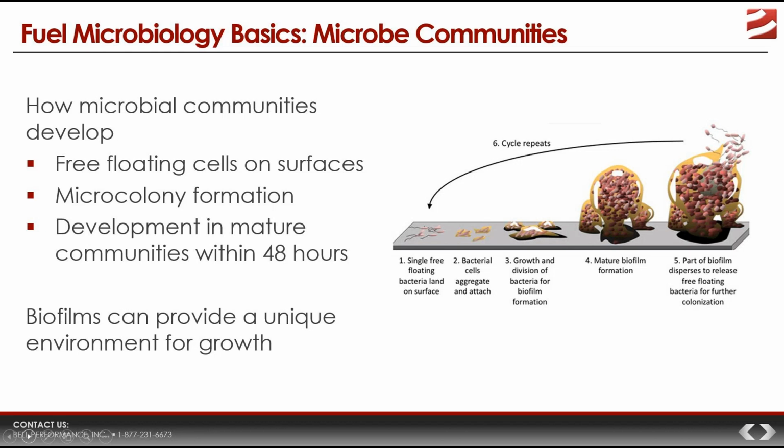Now, how quickly can this happen? This is the surprising thing. All of this can happen from soup to nuts within 24 to 48 hours in a tank. So, going back to biofilm. Contrary to our perception, these slimy masses that we call biofilms are not uniform. They're complex, both in internal composition and, of course, in their distribution within a storage tank.